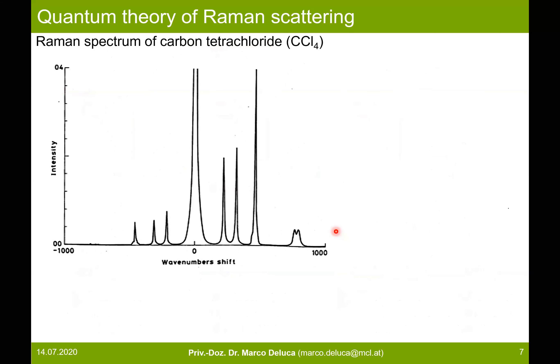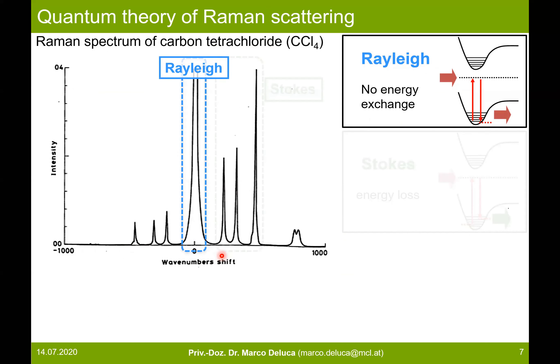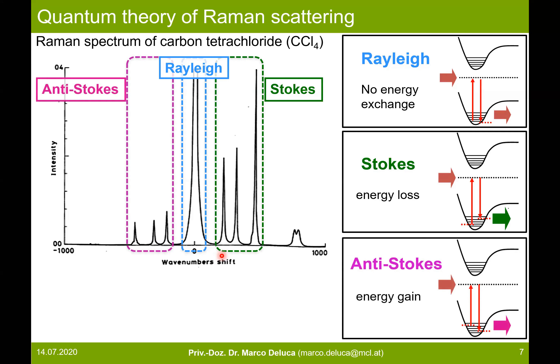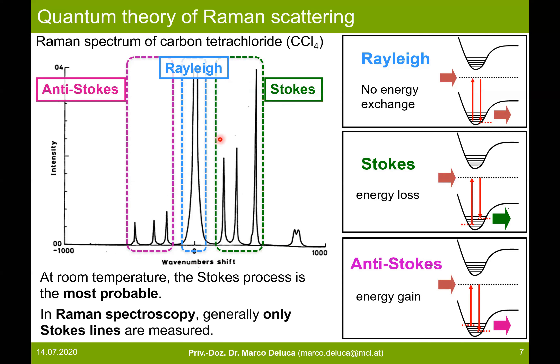A Raman spectrum looks like this: we see very different peaks. If we represent the spectrum in terms of wavenumber shift from the incident radiation, we see a very strong radiation at zero position — the Rayleigh light, the elastically scattered light. Mirrored from it, we see the Stokes lines and the anti-Stokes lines at the same position, but one represents energy loss and the other energy gain. The Stokes lines are the most intense because at room temperature the Stokes process, which originates at the ground state, is most probable, and so in Raman spectroscopy generally only the Stokes lines are measured.